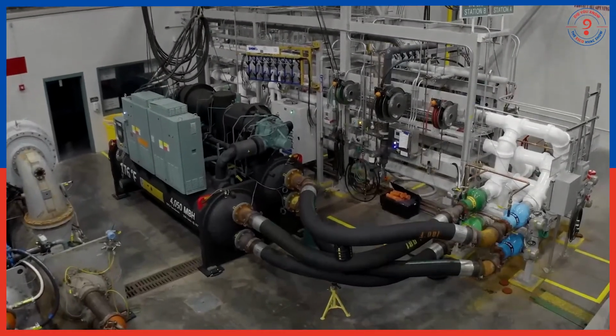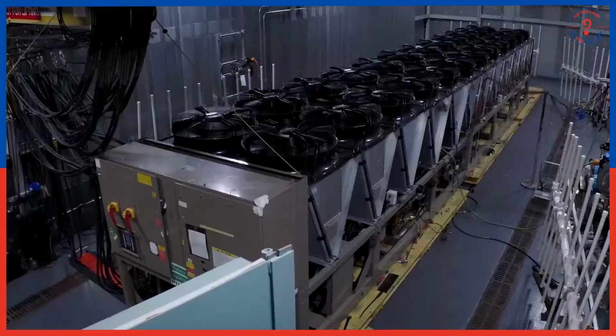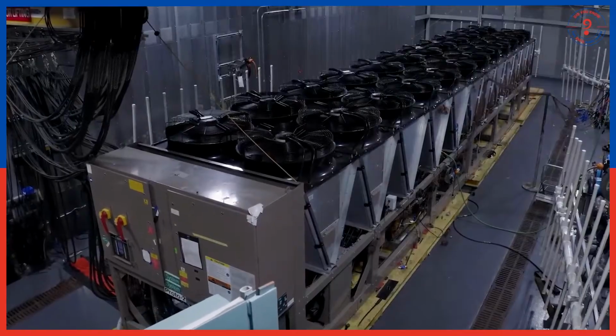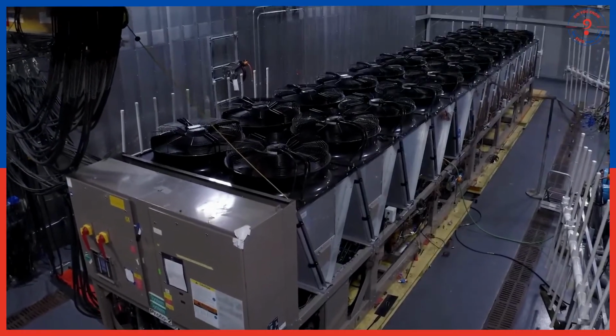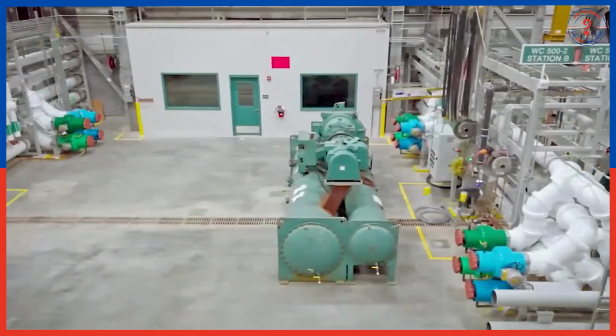Absolutely, 100%. We have over 12 different types of refrigerants that we keep on hand. We've done a big transition to low GWP refrigerants. That's taking the place of older refrigerants, but we've done a lot of baseline testing with the older refrigerants and the newer refrigerants, to make sure that we're truly validating performance before we release these products to manufacturing.